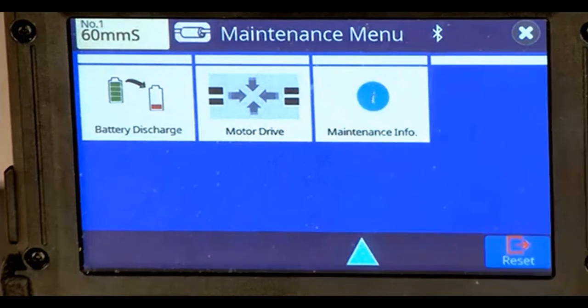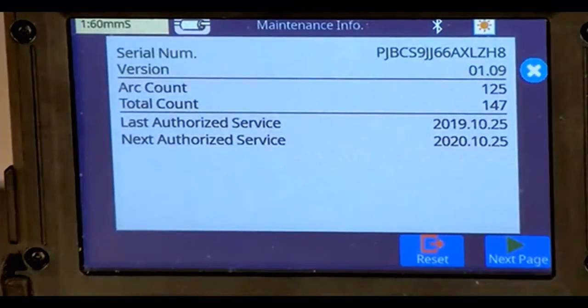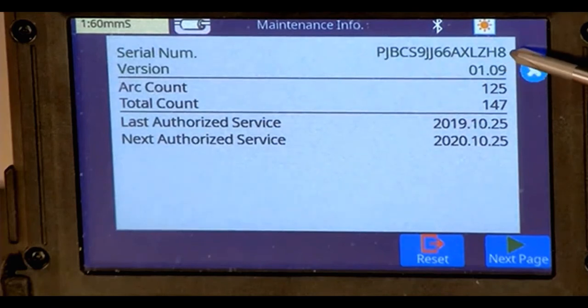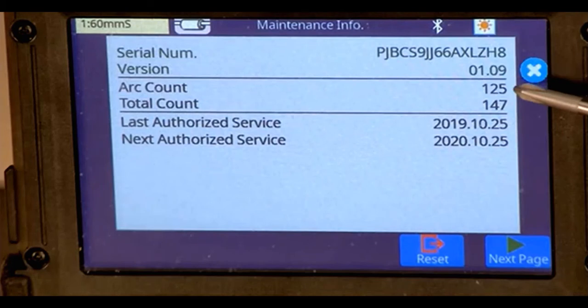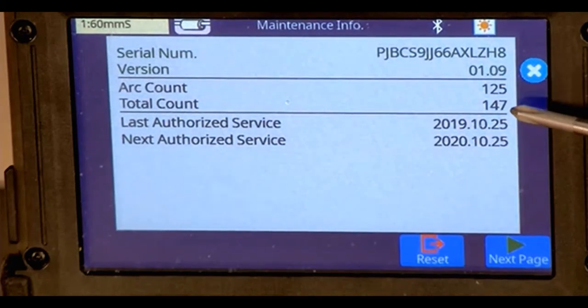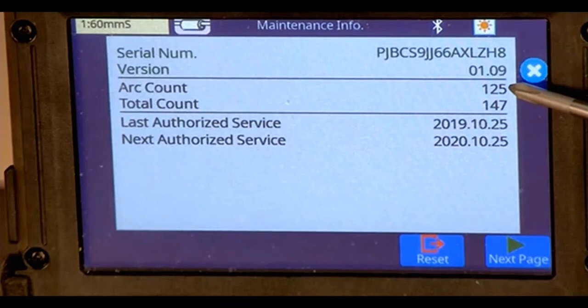This one over here is maintenance issue info. The other thing our service guys would probably ask is what's the serial number of your splicer, and what is the software version. They may or may not be interested in the total arc count—this is the number of arcs this splicer has ever done in its life. This is how many arcs are on the electrodes installed right now, which would be zeroed out when you do an electrode replacement.